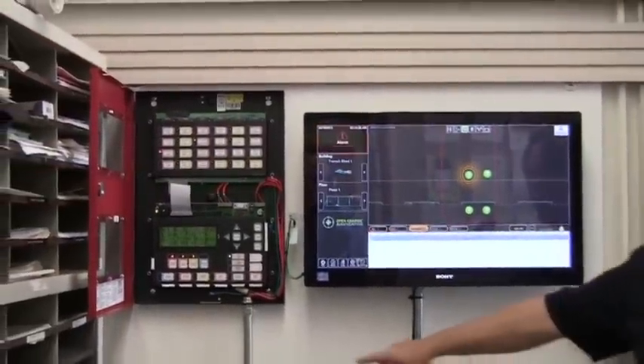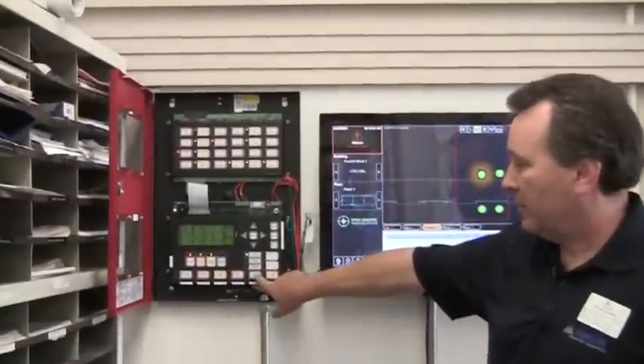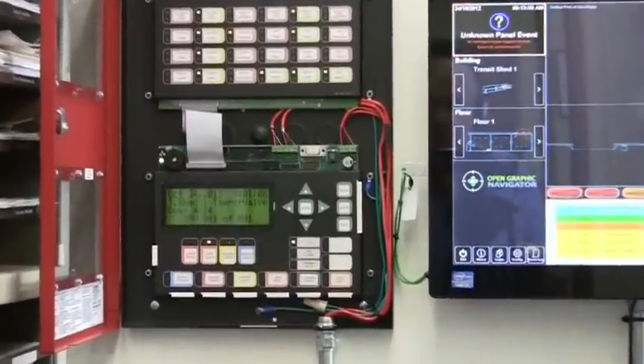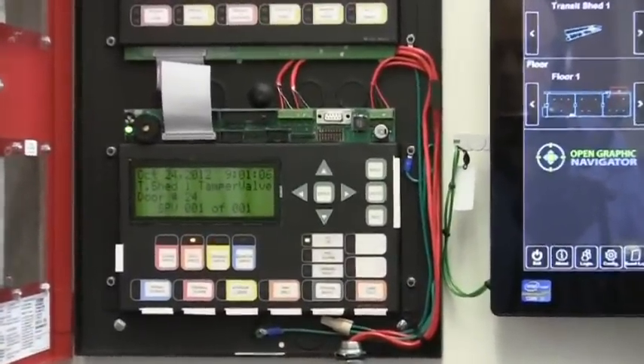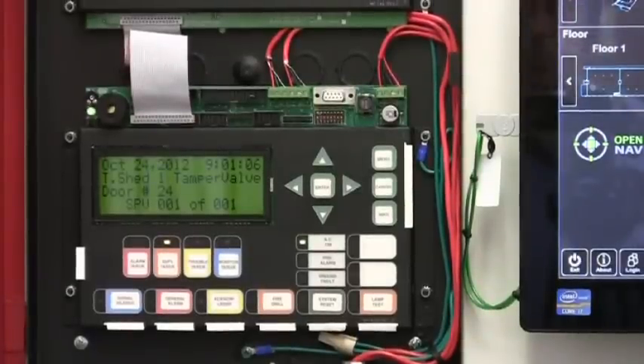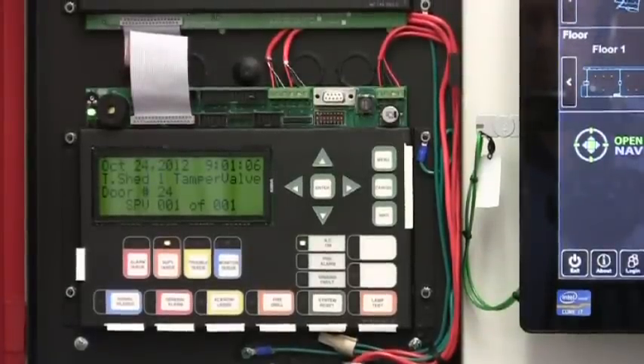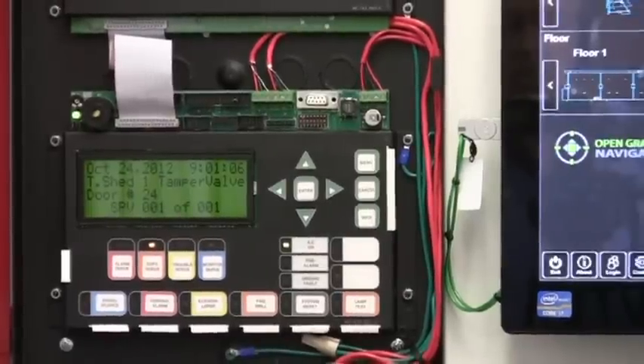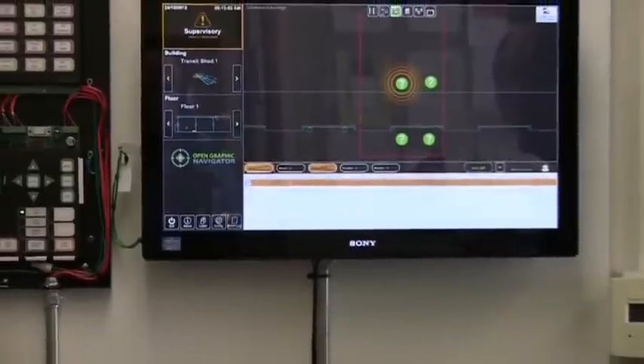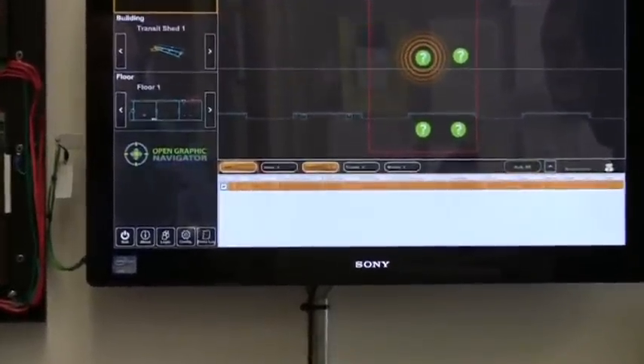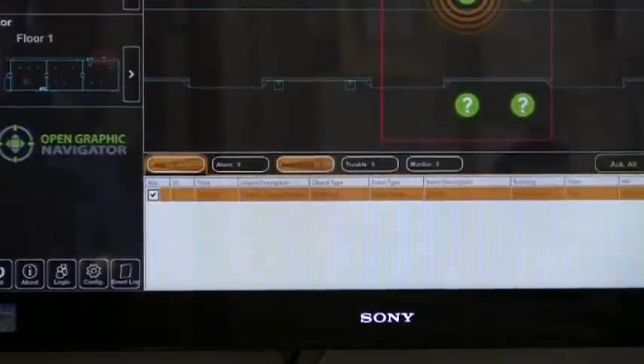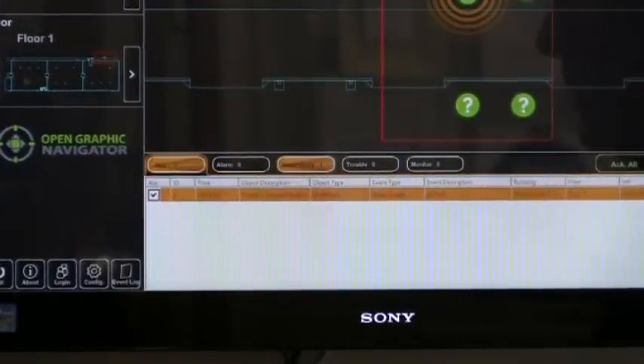We're going to go ahead and restore the system back to normal. System reset on the annunciator will clear the system. If all events have been restored, the system will clear; if events have not been restored, any remaining events will stay in the system. After acknowledging all functions, we notice the supervisory alarm was not cleared — it's still active and needs to be restored in the field.